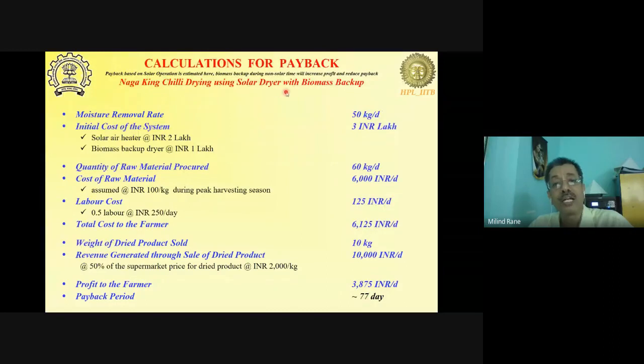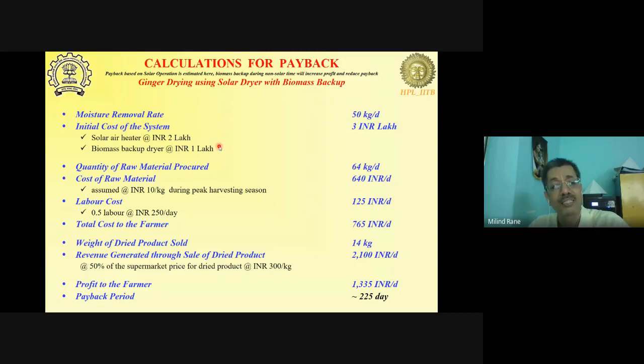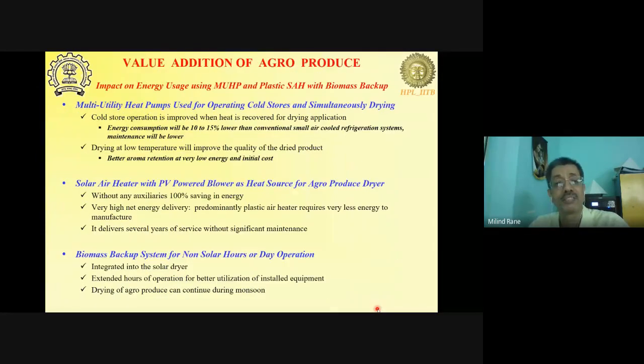Then when we looked at the solar dryer, the one which I just showed based on solar air heaters, the payback was around 77 days for the Naga chilies and around 225 days for the ginger drying application. Okay, the cost of the solar air heaters was 2 lakh. The biomass backed up dryer was around 1 lakh, which my Nagaland partners had developed. So we integrated the solar collectors with that, and the integrated system was a grid independent system. So, value addition for agro produce, basically the impact on energy usage using a multi-utility heat pump and plastic solar air heaters and backup, was demonstrated here successfully.